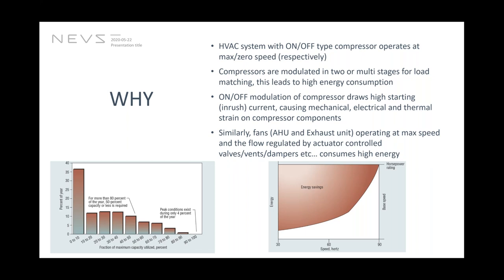So basically, if we take an example of an HVAC system, the old method that originated around the 60s, 70s, even in the Western world, is primarily focused on on-off motors. For example, a three-phase induction motor, which is line start, and you simply switch it on or off. There was no middle ground between the top speed and zero speed. So in the HVAC application, to get different modulation for the compressor, they use multiple compressors and switch them on and off to get different levels of load demand. And this on and off modulation draws quite high current, causes mechanical and electrical as well as thermal strain on the electrical motor as well as compressor components.